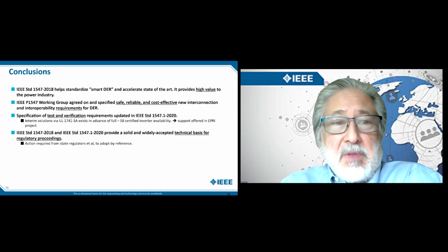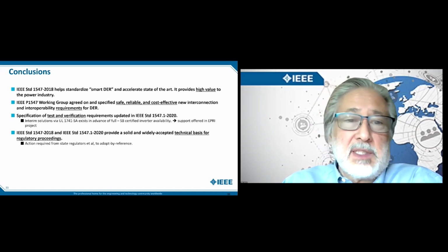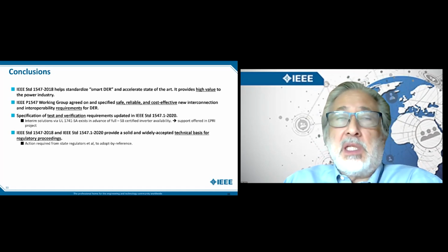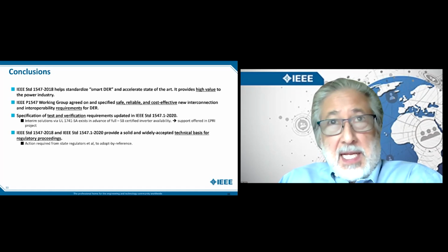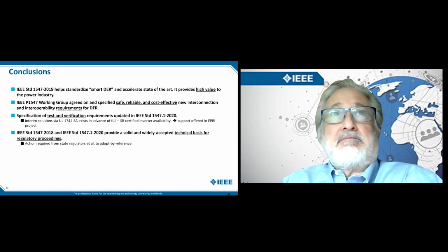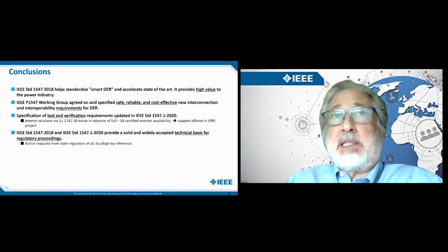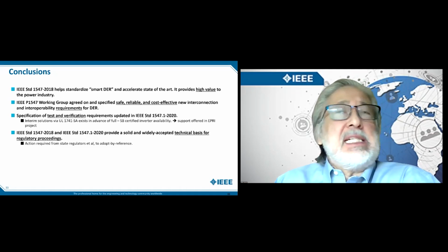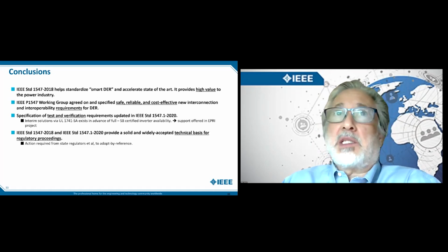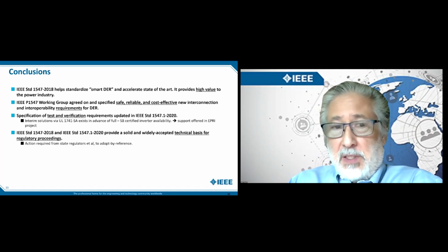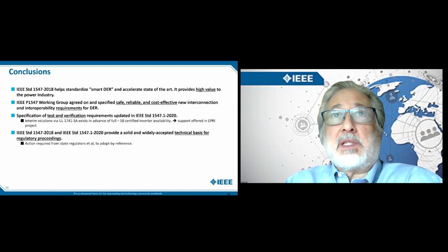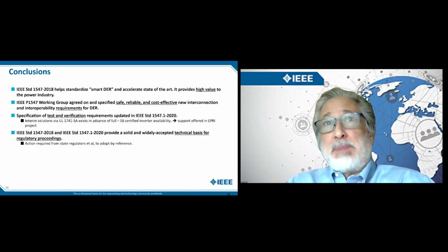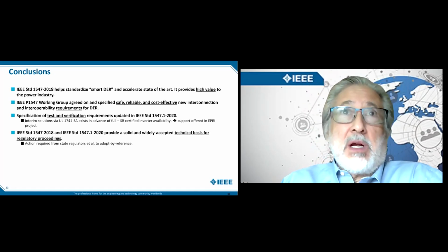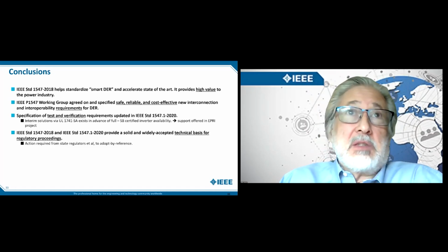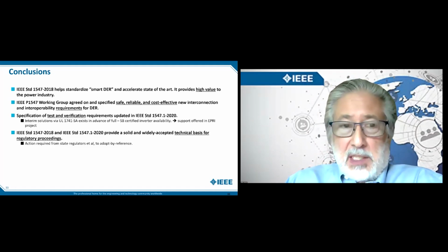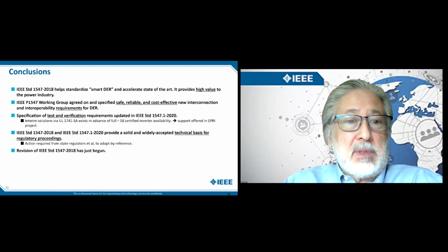Again, there's a real crossover between the 1547 set of standards and the regulatory community. It doesn't have to be just state regulators. Utilities in their procurement specifications can call out 1547. A system integrator, when they go out to their suppliers and manufacturers, can call out 1547 and the related UL 1741 certification. So it's handy for setting that baseline, even at the project level, for what are the minimum performance requirements, and you can draw on the testing certification to come up with a commissioning plan.